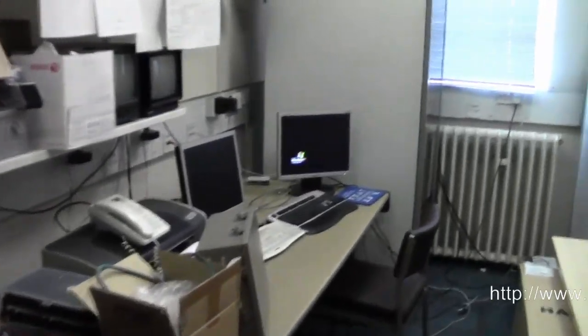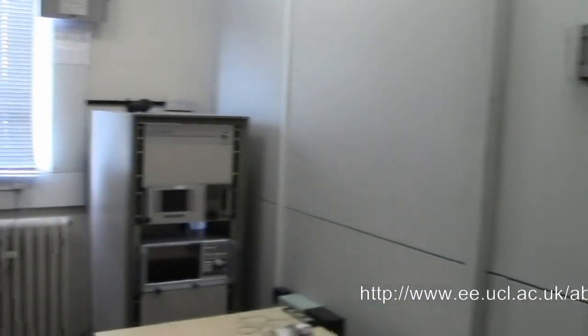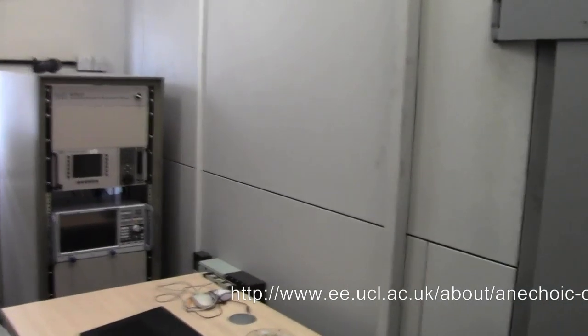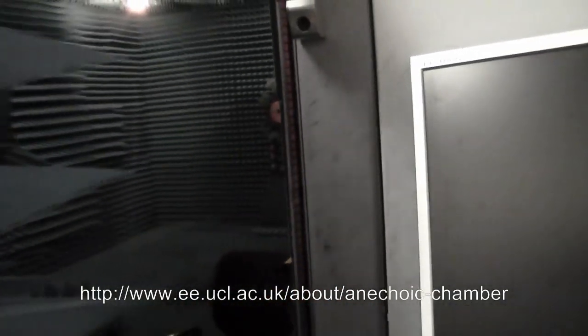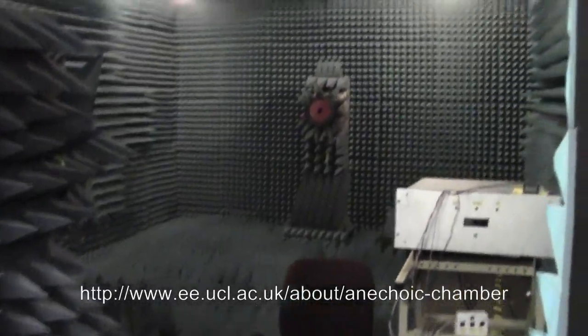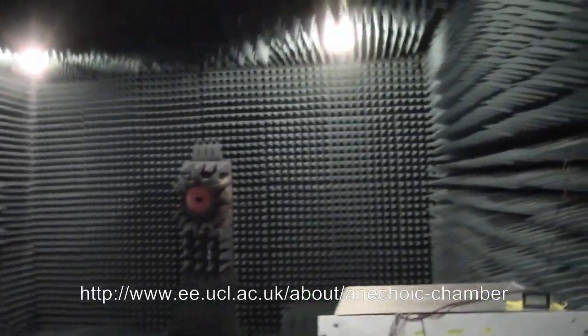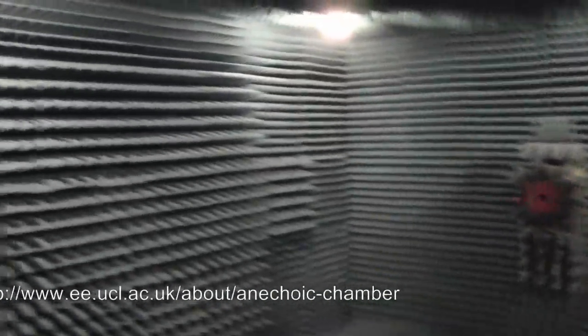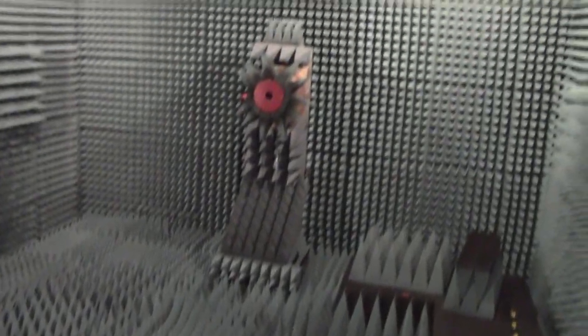Alright, so here we are in the anechoic chamber room, and basically this is for testing all your RF devices, your transmitters, receivers, antennas and so on. Here we go, as you can see it's fully rammed up. You've got your microwave absorption material, your RAM, on all the walls. It's all screen shielded down the back there.